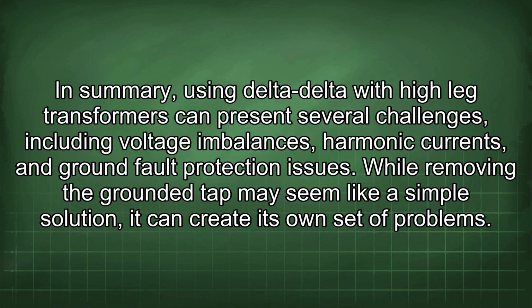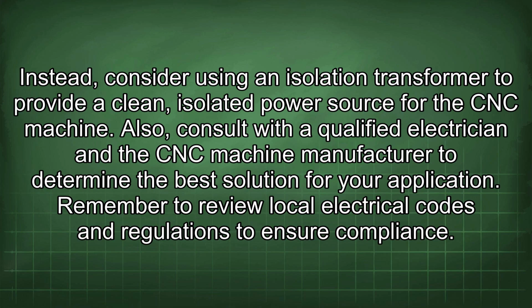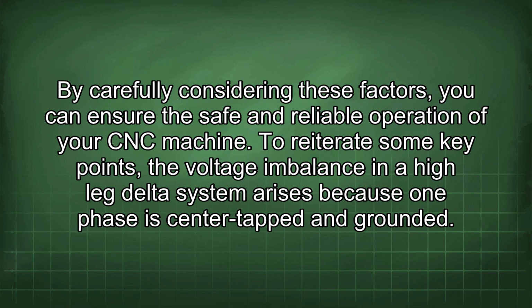In summary, using delta-delta with high-leg transformers can present several challenges, including voltage imbalances, harmonic currents, and ground fault protection issues. While removing the grounded tap may seem like a simple solution, it can create its own set of problems. Instead, consider using an isolation transformer to provide a clean, isolated power source for the CNC machine. Also, consult with a qualified electrician and the CNC machine manufacturer to determine the best solution for your application. Remember to review local electrical codes and regulations to ensure compliance. By carefully considering these factors, you can ensure the safe and reliable operation of your CNC machine.